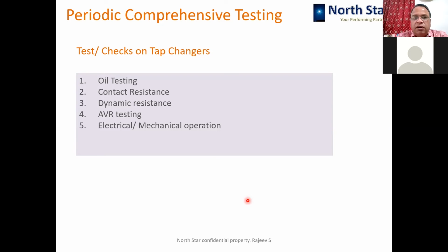So depending upon the oil condition, carbon content, contamination, you can decide on replacement of the oil, because normally in OLTC, especially in tank OLTC, the oil quantity is very little. So you can replace it with the new one. And out tank OLTC, you can go for filtration. And maybe after a few years of working, you can think of replacement of the oil. But again, in case of OLTC, I would suggest that you follow the O&M manual of the OLTC supplier.